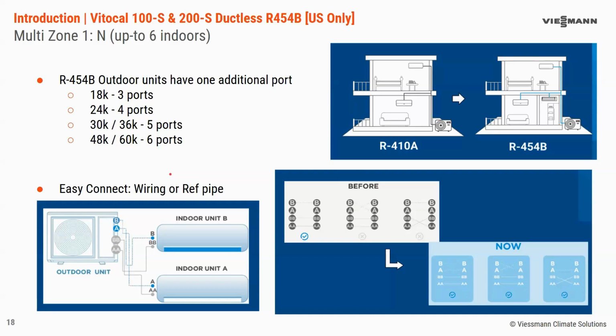And what's shown below is a feature that's built into the product, not encouraging necessarily bad behavior, but if in a multi-zone application there is a miswiring or mispiping, there is a corrective feature built in where the unit can detect the correct indoor unit and switch communication as needed. It's not going to fix major installation errors, but that is a feature that improves the installation. Of course, the recommendation is to follow the installation practices and wire and pipe correctly.